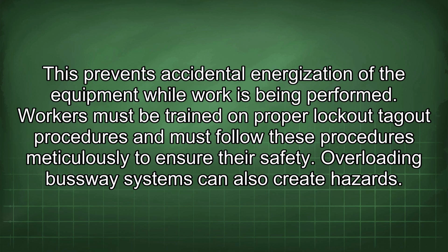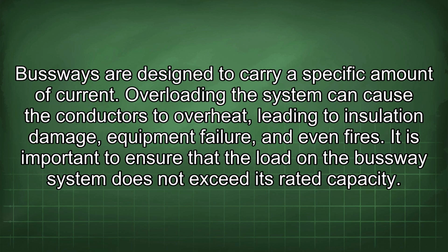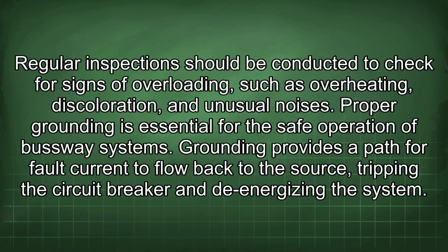Overloading busway systems can also create hazards. Busways are designed to carry a specific amount of current. Overloading the system can cause the conductors to overheat, leading to insulation damage, equipment failure, and even fires. It is important to ensure that the load in the busway system does not exceed its rated capacity. Regular inspections should be conducted to check for signs of overloading, such as overheating, discoloration, and unusual noises.